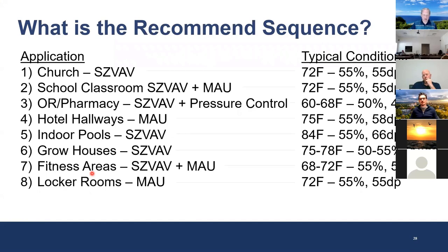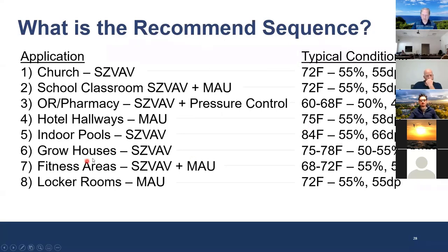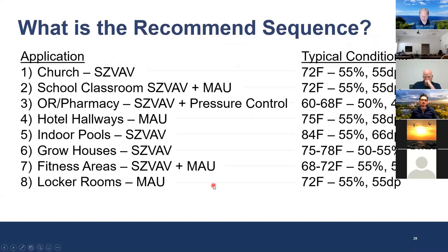Finally, what is the recommended sequence? We have churches, classrooms, hotel hallways — 75°F at a 58°F dew point, basically telling guests 'go to your room' where they have independent control. Indoor pools at a 66°F dew point. Grow houses range from 75–78°F at 50–55% RH. Fitness areas: single zone VAV, heavy load when occupied and no load when unoccupied, plus makeup air component — a spin room generating tremendous CO2, targeting 68–72°F at 55% RH with lower dew points for comfort. Locker rooms: makeup air unit, 72°F at 55% RH, 55°F dew point.